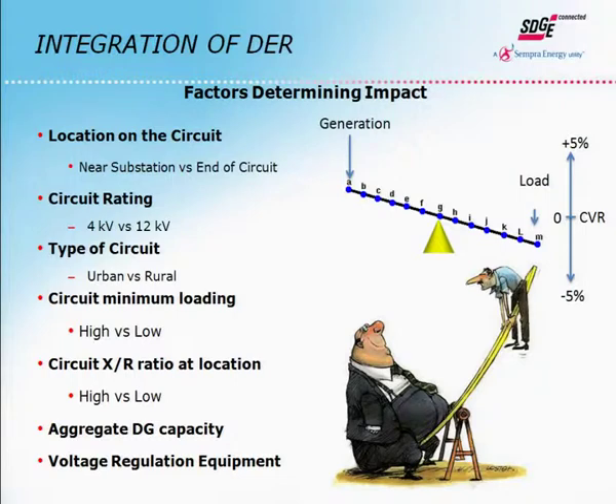Location on the circuit is important, whether it's near the substation or at the end of the circuit. We've seen pretty much 100% loaded or PV generated circuits where the ratio of PV to load is 100%, but it's right at the substation on a very stiff feeder, and we haven't really seen a lot of problems at this point in time. What is the circuit rating, 4,000 volts or 12,000 volts? What type of circuit is it? Urban versus rural: urban tends to be much shorter, much more intertie, much bigger conductors. Rural tends to be much longer circuits going various places. What's the minimum loading? If you got lots of load on the circuit, the issues aren't as bad as they would be if the loading was much lower. X to R ratio, this is basically the ratio of the reactance to the resistance.